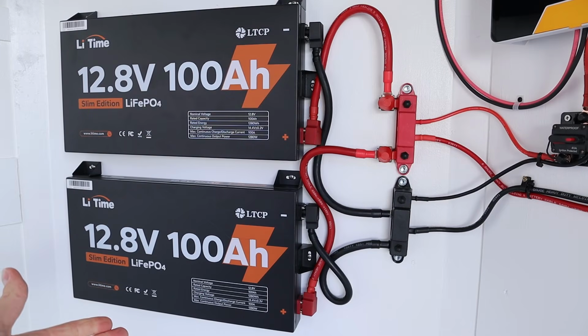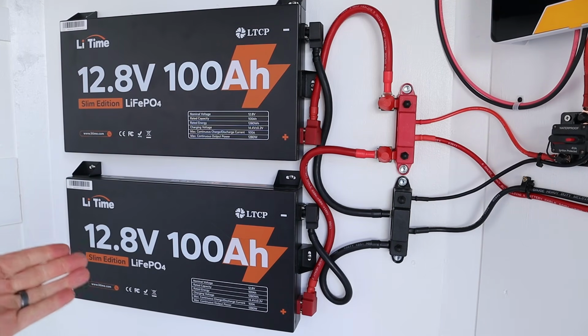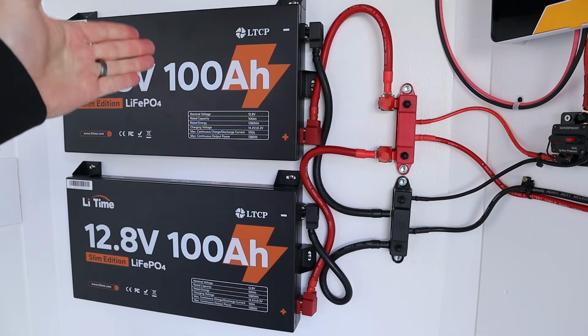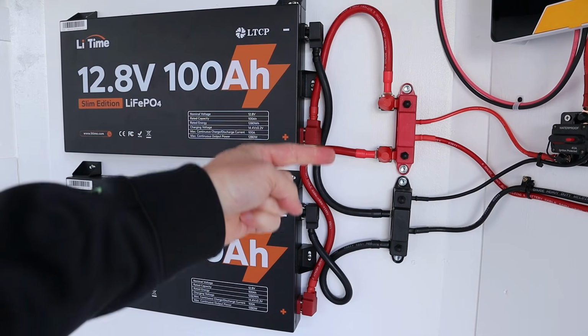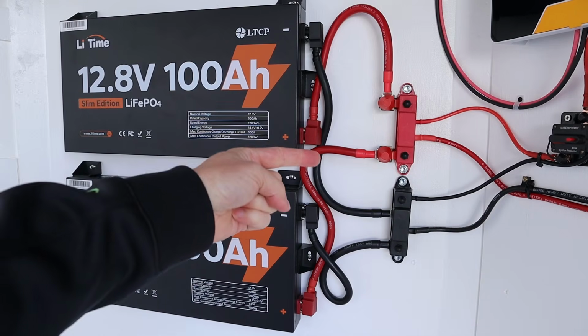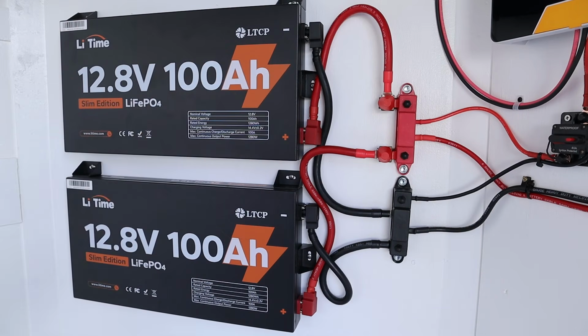These slim batteries support both parallel and series connections, so whether you have a 12 volt, 24 volt, or 48 volt system, you can wire them together accordingly. Because I have a 12 volt system in my trailer, I've wired both together in parallel using these bus bars. I have 2 150 amp fuses off the positive bus bar, and I'm using 1/0 cable, which is good for 150 amps continuous.